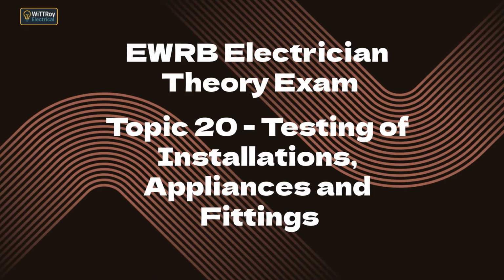3. Insulation resistance. Instrument: insulation resistance tester, 500V or 1000V depending on system. 4. Polarity. Instrument: continuity tester or multimeter. 5. Earth loop impedance, ELI. Instrument: earth loop impedance tester. 6. Prospective short circuit current, PSC. Instrument: PSC tester or ELI/PSC combined tester. 7. Verification of voltage drop. Instrument: calculation or measurement with multimeter.